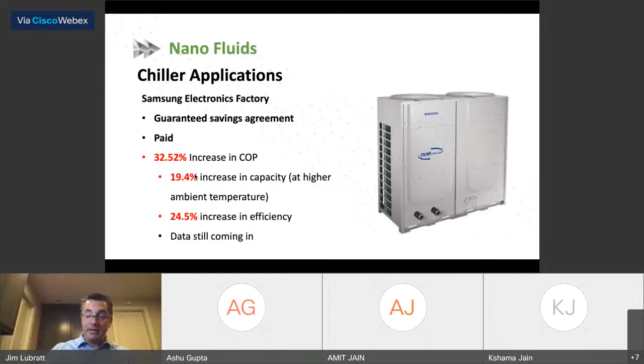The study resulted in, and I'll bring up on my last screen the data, a 32% increase in COP, coefficient of performance. What that means is it had an increase in efficiency of 24%, but more importantly, because we increase the surface area of heat exchangers by adding nanoparticulate to the fluid, we increase the capacity of the existing equipment by 19.4%.